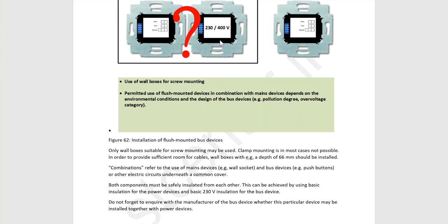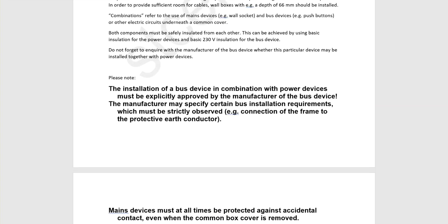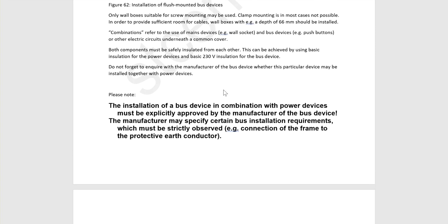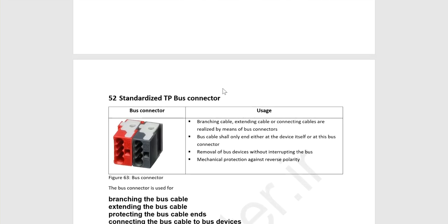Remember that these devices, this keypad or sensor, most of the time in KNX, it has the IP environment equal to 20, so you cannot put it in a harsh environment, I mean with so much dust or moisture or whatsoever. So install it in the exact environment that the datasheet said. It is important. And as the book said, the installation of a bus device in combination with the power device must be explicitly approved by the manufacturer of the bus, so it should be mentioned in a data sheet.